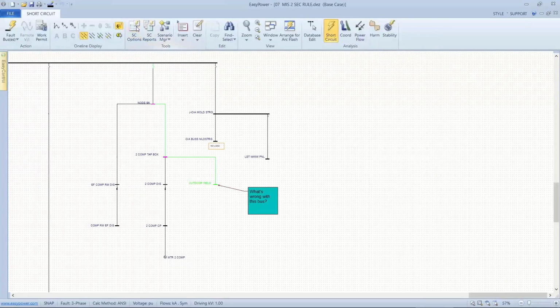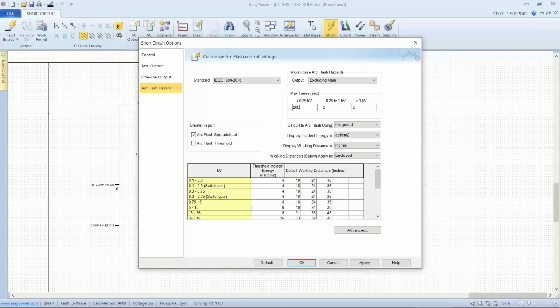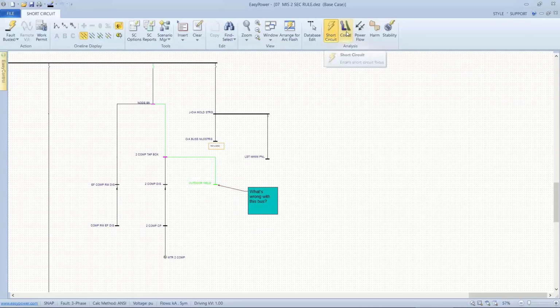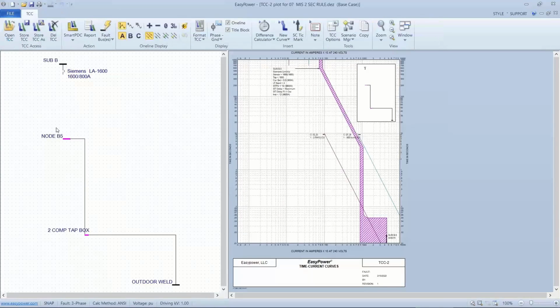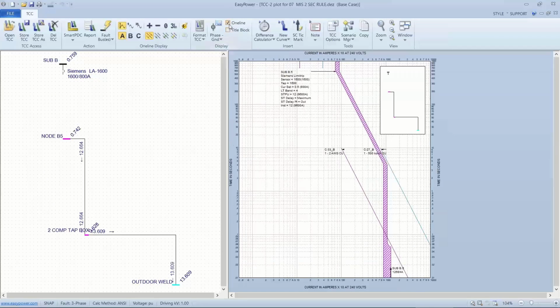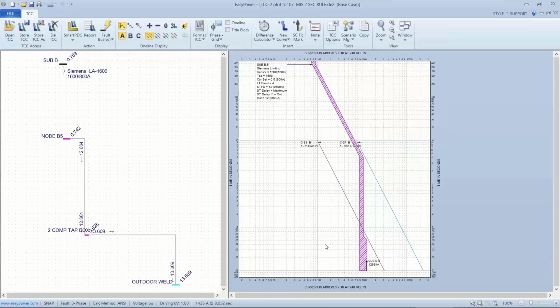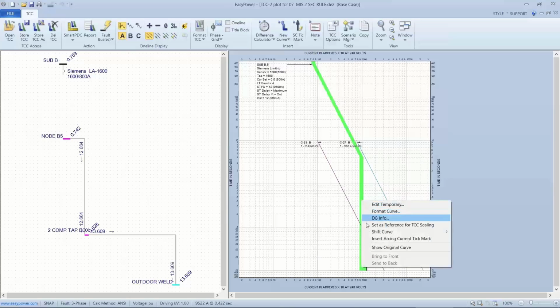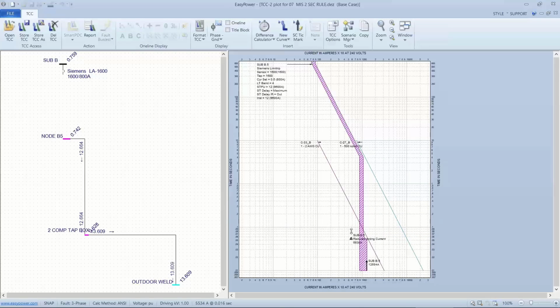Go to short circuit, setup. Let's take the 2 seconds out of the equation by extending the time, and then go back and plot the same portion of our one line. Again, if I fault this bus, I can see the breaker is being tripped at a relatively quick time. But if I look to see what my arcing current is now, it falls to the left-hand side because it's a reduced arcing current as dictated by the standard, a more conservative result. And it takes almost 20 plus seconds. So that's why artificially limiting it to 2 seconds was negating the fact that this is miscoordinated.